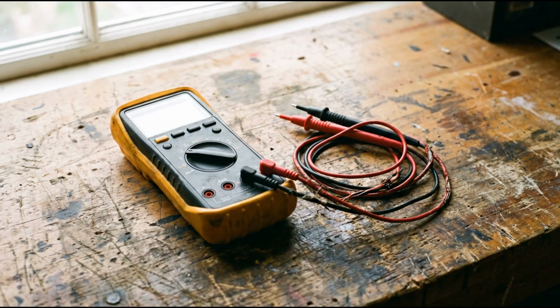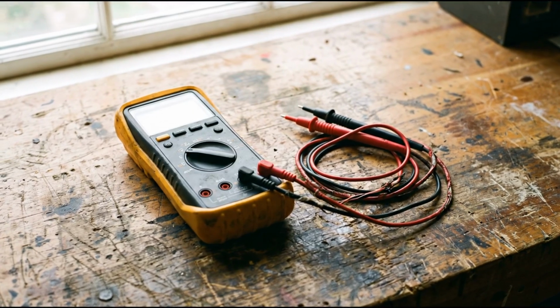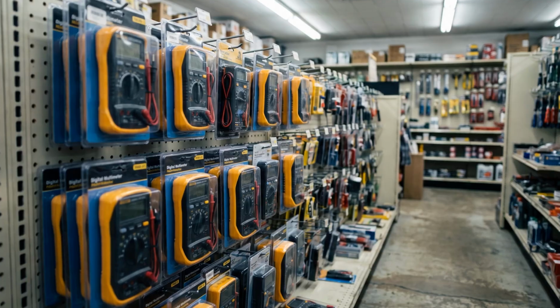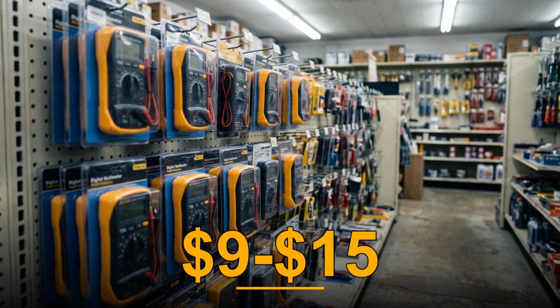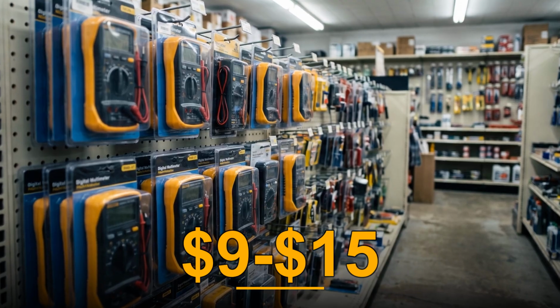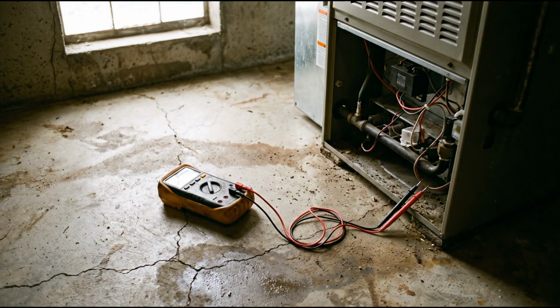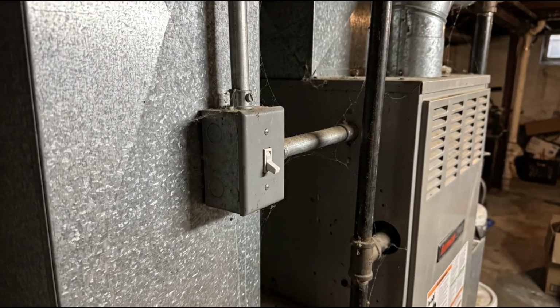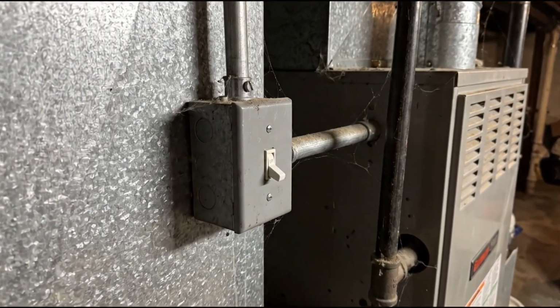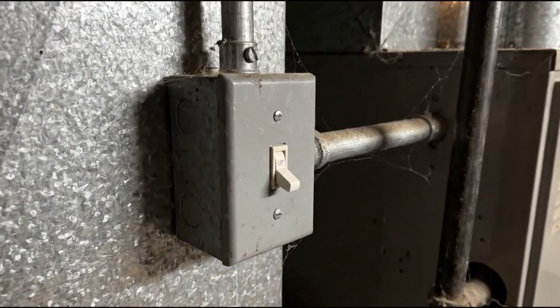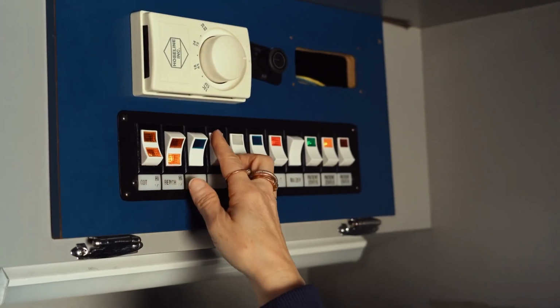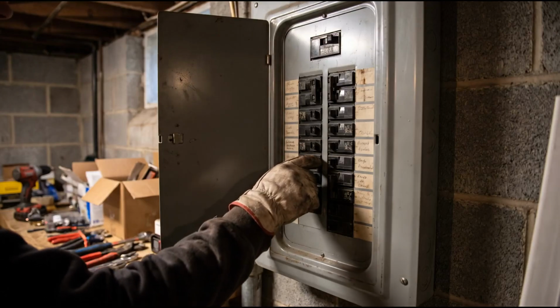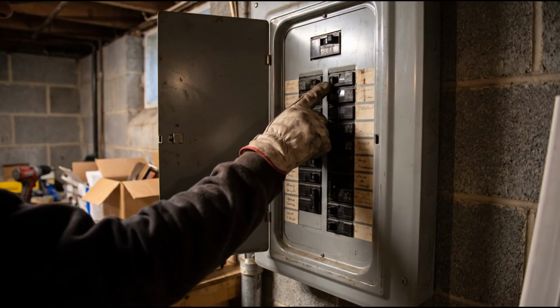Step 3. The test. Do not skip this. The meter is the difference between knowing and guessing. You need a basic multimeter, $9 to $15 at any hardware store, and it will serve you for every video I ever make. First, kill the power. There is a switch on or beside the furnace that looks like a light switch. Flip it off. If you cannot find it, flip the furnace breaker in the panel.